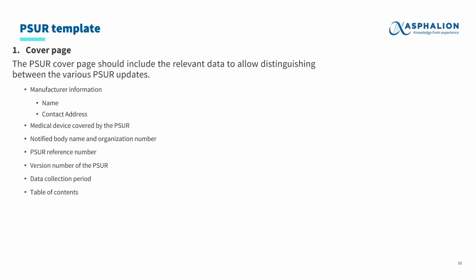First of all, the PSUR has to have a cover page, which should include all relevant data to allow distinguishing between the different updates of the PSUR. So in this cover page, we should include manufacturer information, at least name and contact address, also the medical device covered by the PSUR, the notified body name and organization number that will review our PSUR, the PSUR reference number, which should be assigned by the manufacturer, the version number of the PSUR to maintain the traceability of the document, the data collection period covered by the PSUR, and a table of contents.